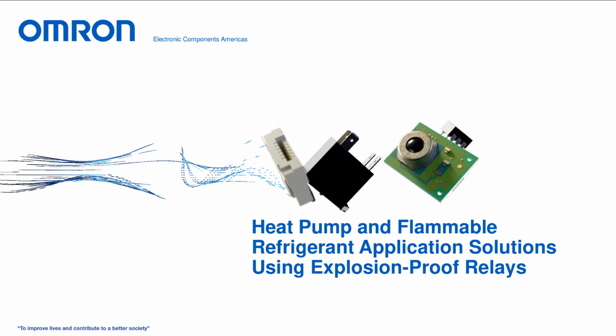This one's from Andre asking, you mentioned that only flux protection doesn't protect against gas. So even if the relay operates with a current lower than 16 amps, if the environment of the relay is exposed to flammable gas, must the relay be sealed? So this is where we get into how we attain the certification for 16 amp and below switch. We do have unsealed products that are certified. They are flux protected, unsealed products that are certified as explosion proof.